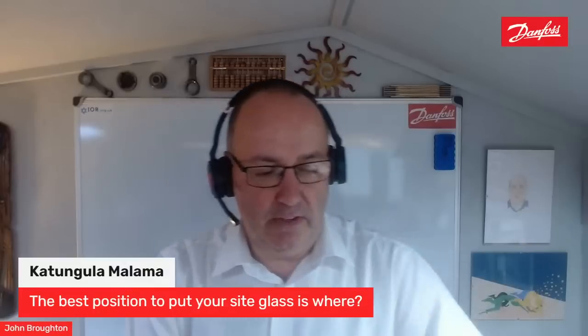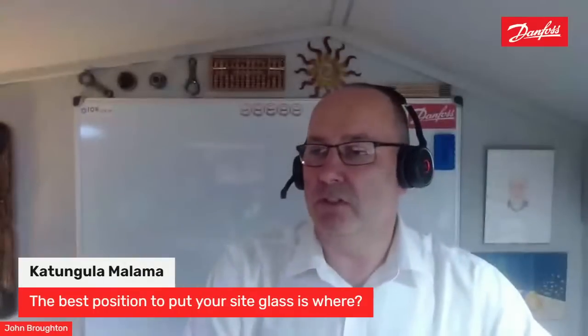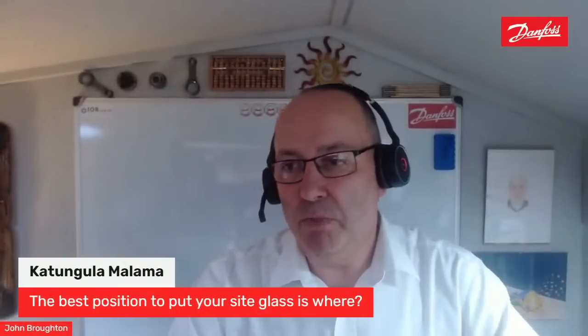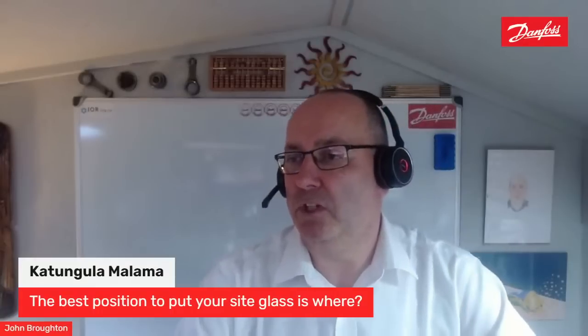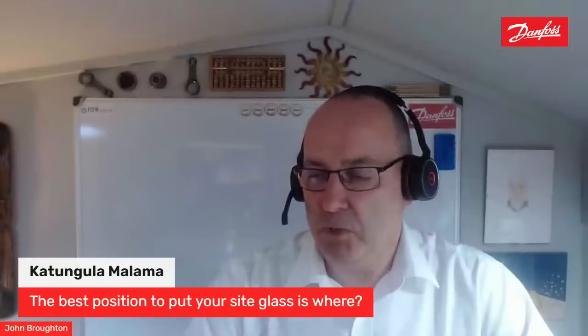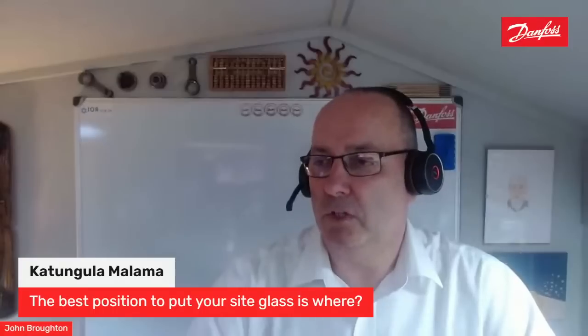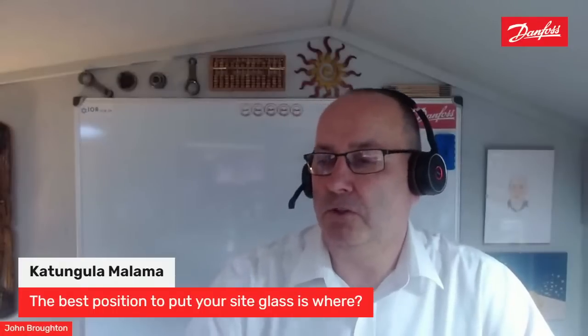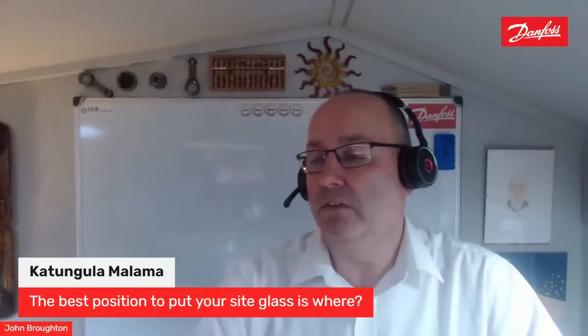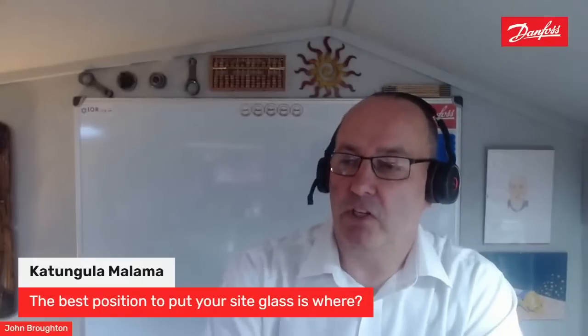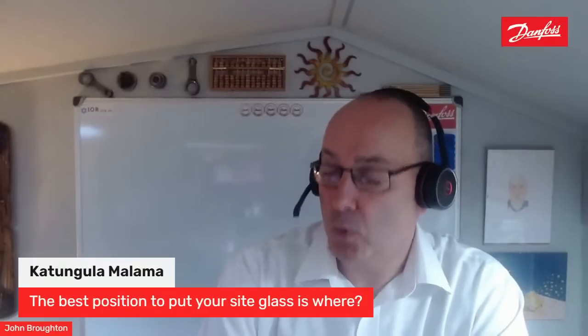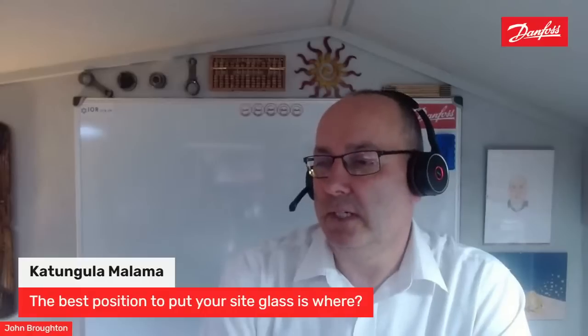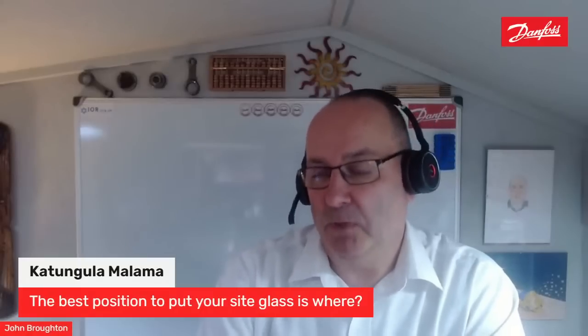So, best position to put your sight glasses where? Now, I'll annoy everybody who makes condenser units, including Danfoss. The best position to put your sight glass is in front of the expansion valve, because at the expansion valve we want a full column of liquid. That's the best place to actually check the quality and the quantity of liquid that we've got. So yeah, best place is there.